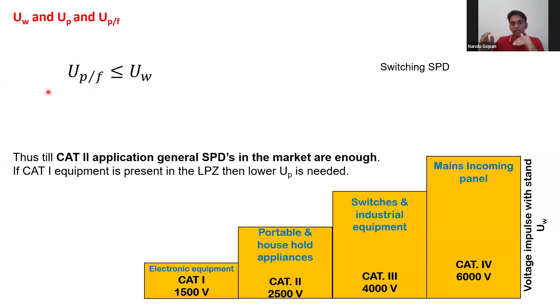This UP is what you can find in all SPDs. You can take an SPD and check that UP will be 1.5 kV. In the National Building Code, they have given that you are supposed to have UP not more than 1.5 kV. So it should be lower than or equal to this. If you find any SPD with more than 1.5 kV, you just throw it out, because it is not going to protect your equipment. Rather, the equipment is going to protect your SPD. So all SPDs should have a UP of 1.5 kV.